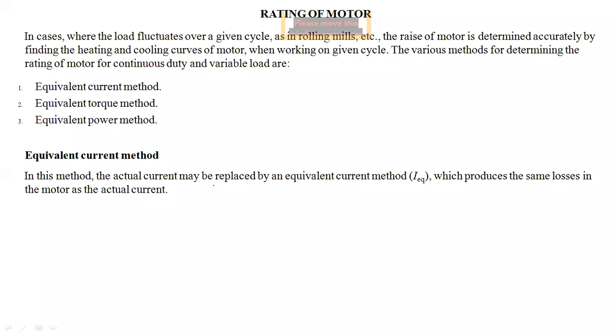So how are these methods going to happen? The first one is the equivalent current method. Whatever actual current you supply to your motor is replaced with the equivalent current, I equivalent. By replacing the actual current with the equivalent current, it will produce the same losses that occur when the actual current passes to the motor.